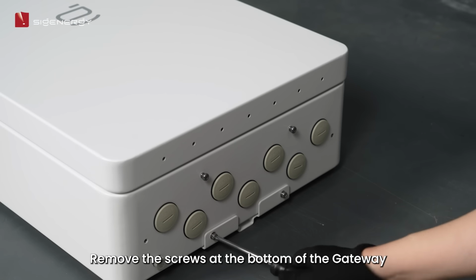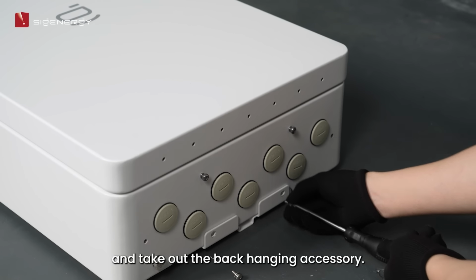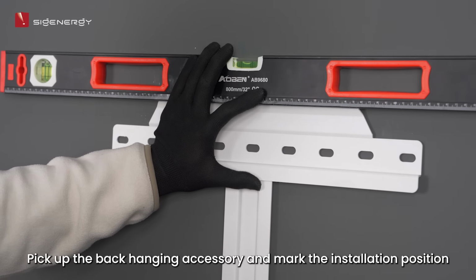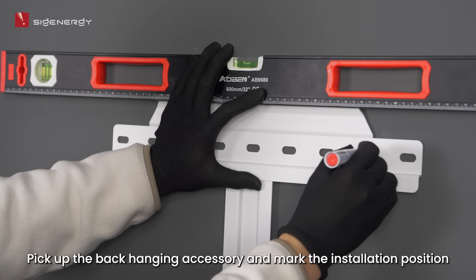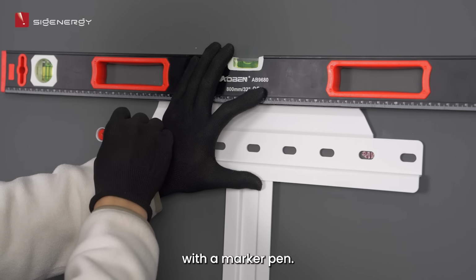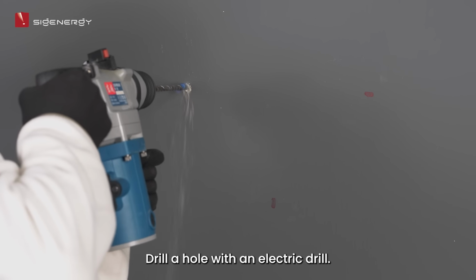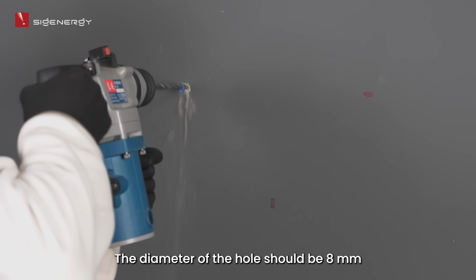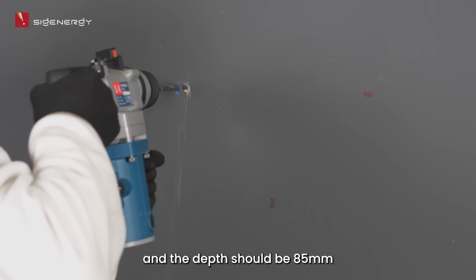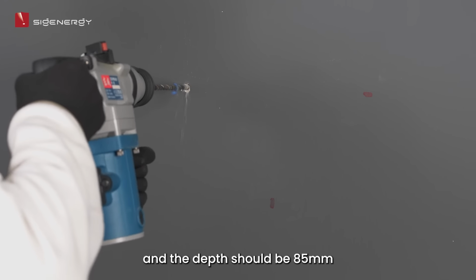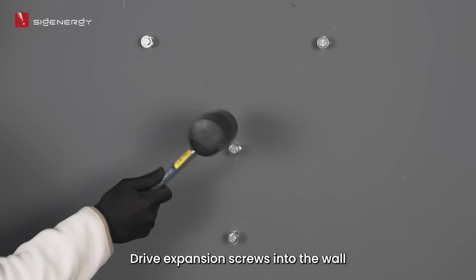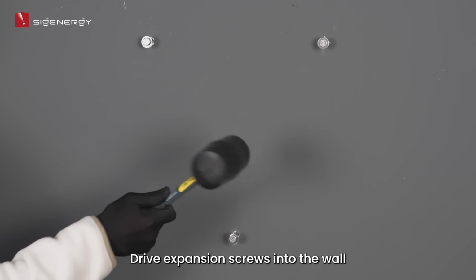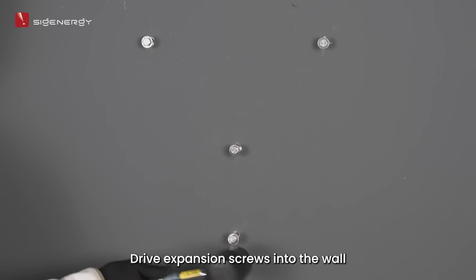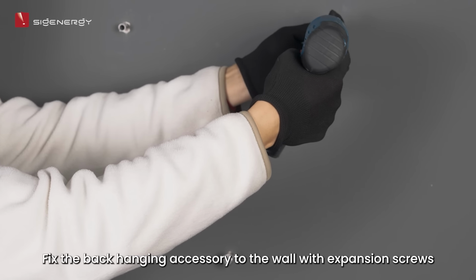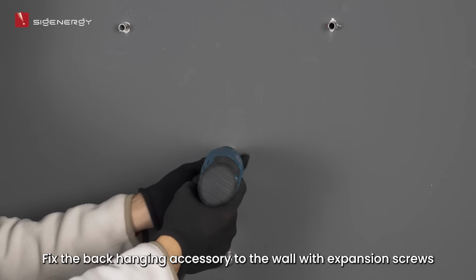Remove the screws at the bottom of the gateway and take out the back hanging accessory. Pick up the back hanging accessory and mark the installation position with a marker pen. Drill a hole with an electric drill. The diameter of the hole should be 8 millimeters and the depth should be 85 millimeters. Drive expansion screws into the wall. Fix the back hanging accessory to the wall with expansion screws.